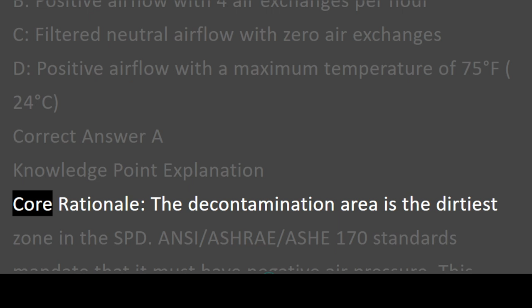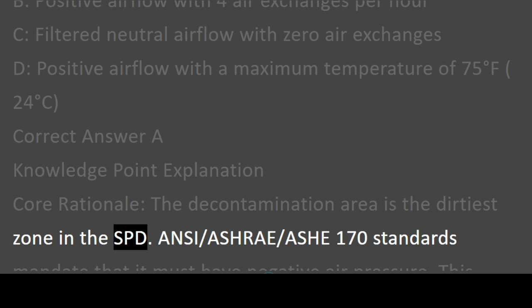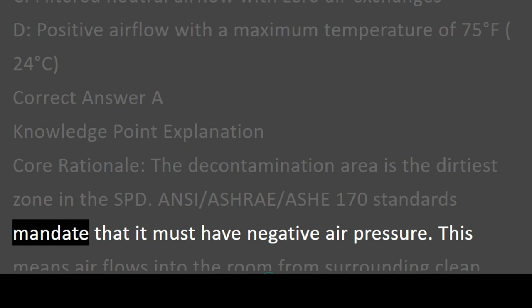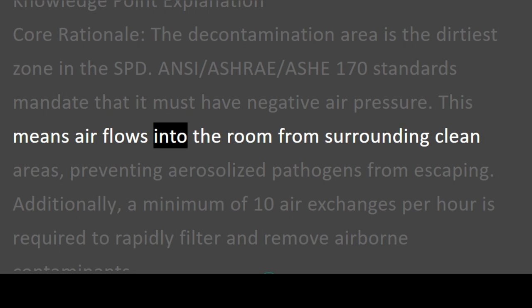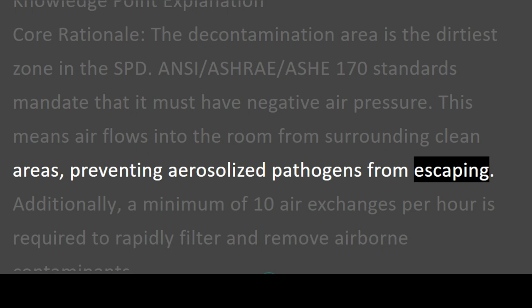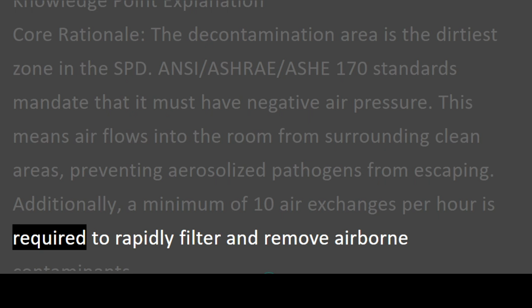Correct answer A. Knowledge point explanation. Core rationale. The decontamination area is the dirtiest zone in the SPD. ANSI/ASHRAE/ASHE 170 standards mandate that it must have negative air pressure. This means air flows into the room from surrounding clean areas, preventing aerosolized pathogens from escaping. Additionally, a minimum of 10 air exchanges per hour is required to rapidly filter and remove airborne contaminants.